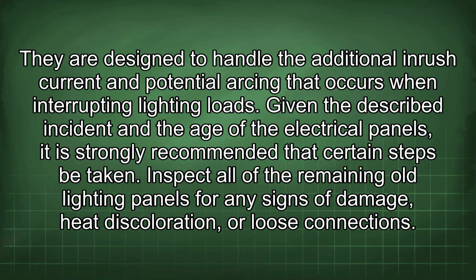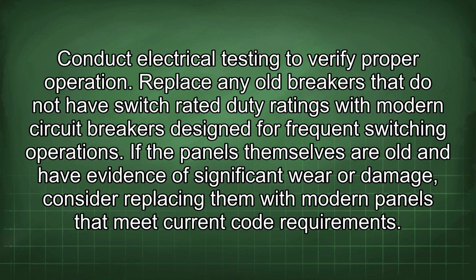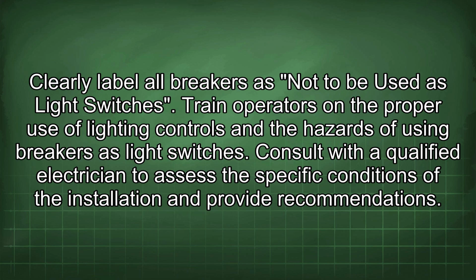Inspect all of the remaining old lighting panels for any signs of damage, heat discoloration, or loose connections. Conduct electrical testing to verify proper operation. Replace any old breakers that do not have switch-rated duty ratings with modern circuit breakers designed for frequent switching operations. If the panels themselves are old and have evidence of significant wear or damage, consider replacing them with modern panels that meet current code requirements. Clearly label all breakers as not to be used as light switches. Train operators on the proper use of lighting controls and the hazards of using breakers as light switches.